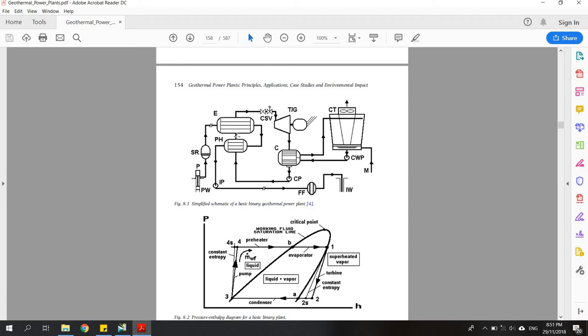The geothermal brine will give heat to the working fluid — in this case isopentane — and the isopentane will change phases from liquid phase to gas phase. After that, the geothermal brine will be delivered to the second heat exchanger, which is the preheater, where the working fluid will be preheated before it is heated in the evaporator. After that, the working fluid will have 100% vapor phase and it will be used to rotate the turbine.